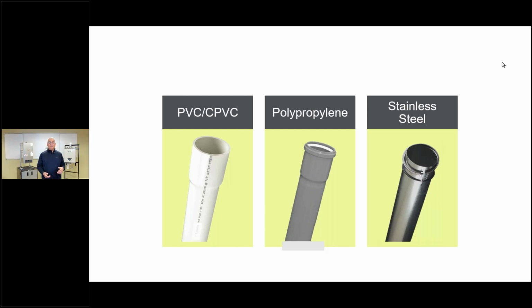So I was thinking about this. This could be the rule of 20, if you want to think about it that way. Whatever my supply water temperature is going to be, my flue gas temperature will be 20 degrees hotter. So if that's the case and you run your system at 120 degree supply water max, PVC is a home run, not a problem. But if my appliance is also going to do domestic hot water, and my domestic hot water load is a good sized load, quite often that appliance is going to high fire. So if it's high firing to its max of say 170, 180, now you're talking a flue gas temperature of 200 degrees. You are well past the allowable temperature on PVC pipe.